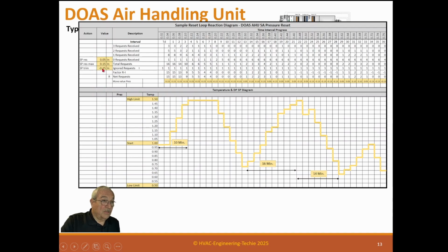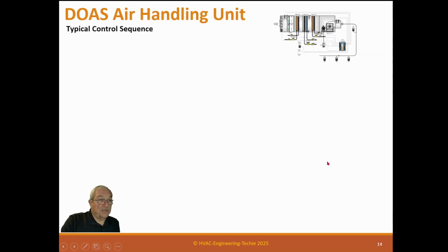So you can go down faster, you can go up faster, depending on what you want to do. But I like this under a half hour; 10 to a half hour is great. Over a half hour is not good. Under 10 is probably too fast. It's going to provide some hysteresis in the system. And that's just the way I look at the systems as I'm testing what I've designed it to be.